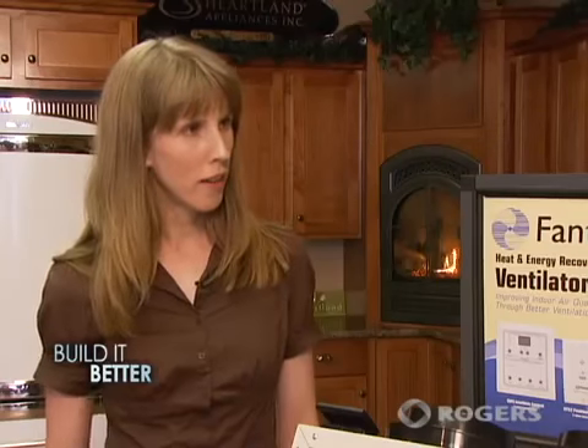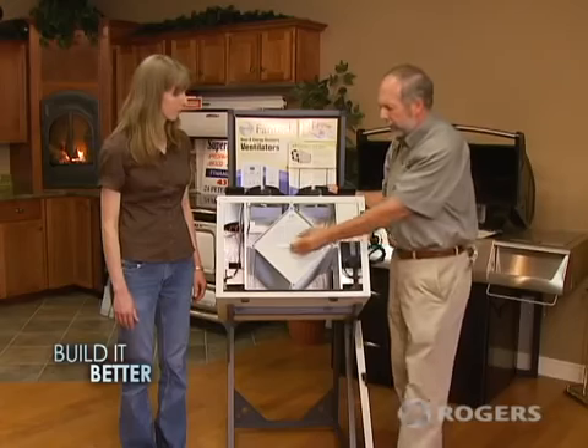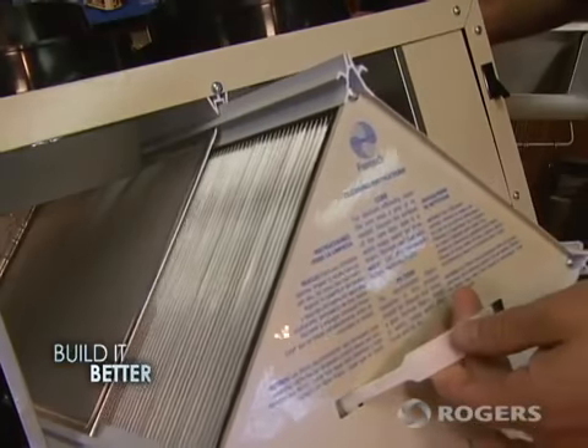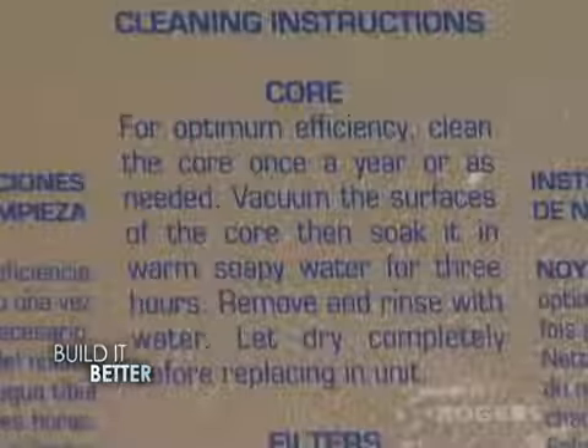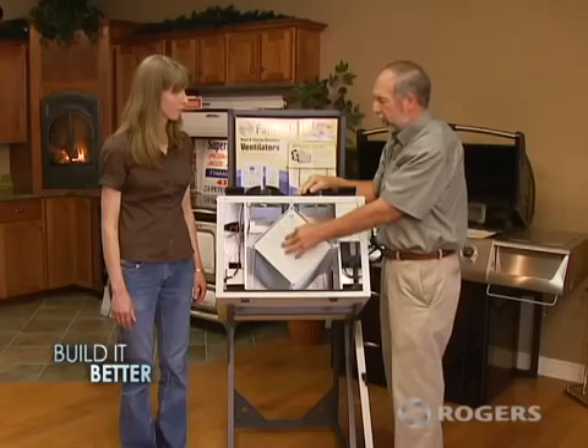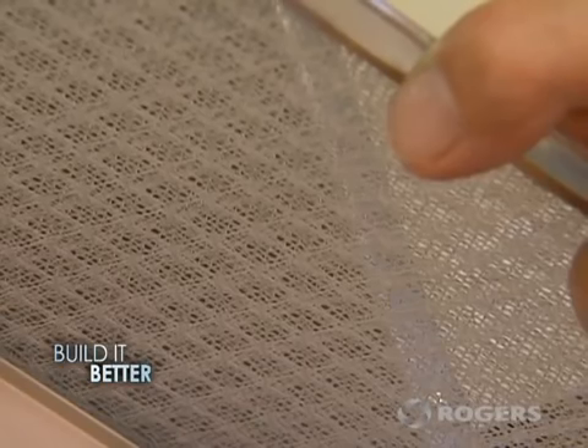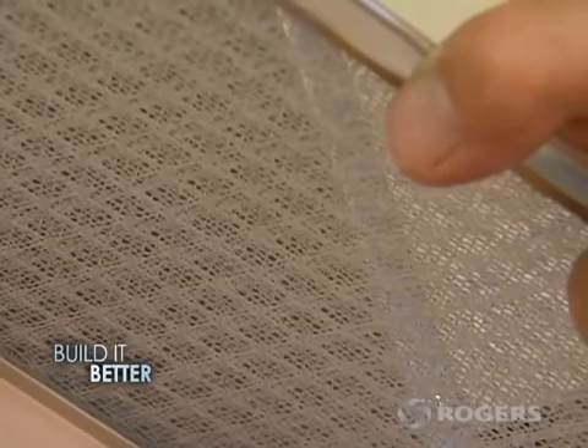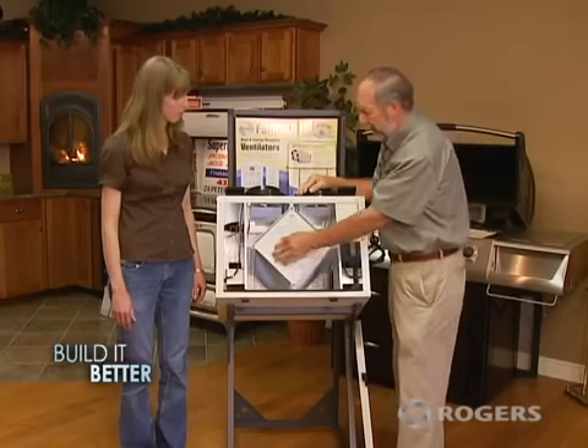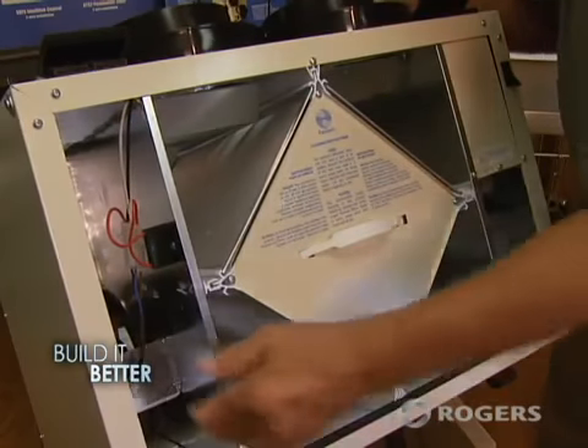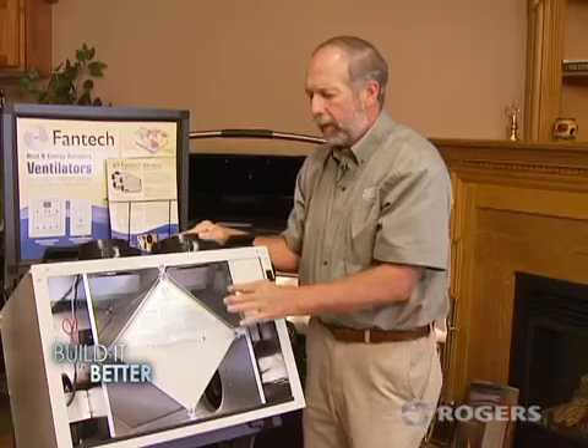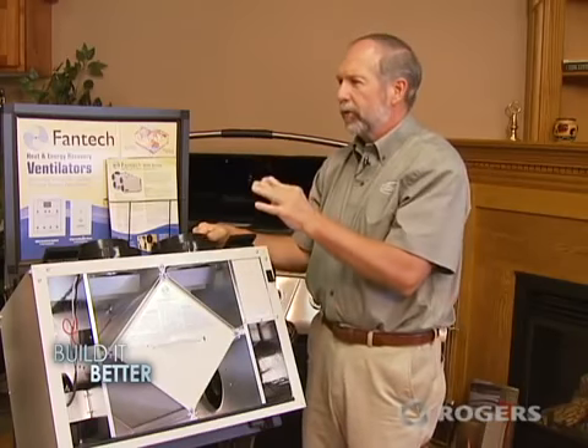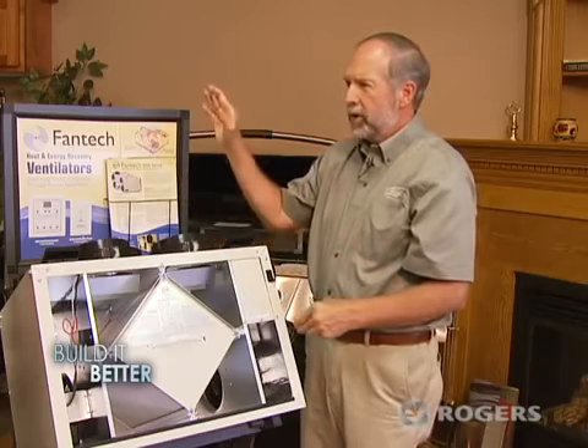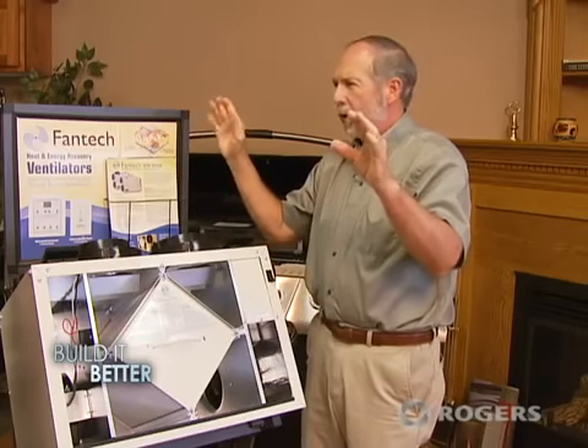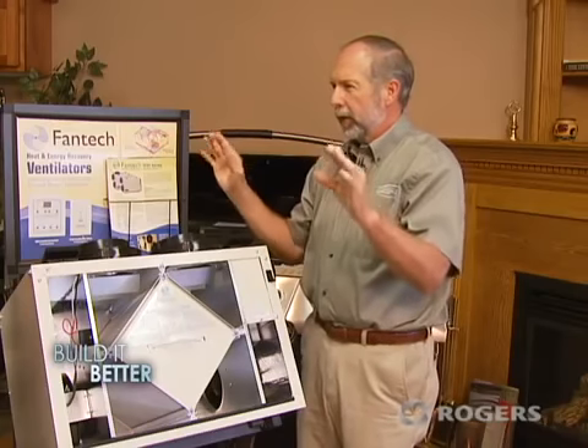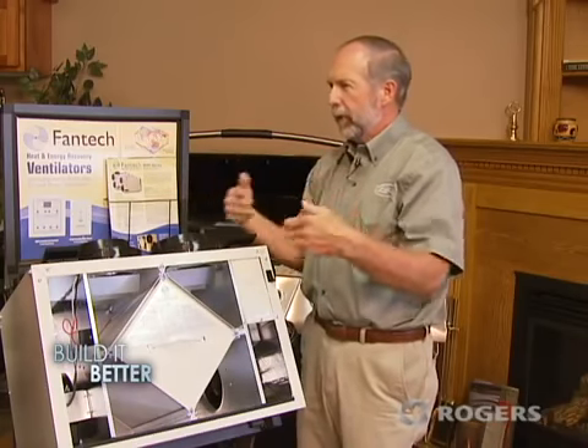Is there much involved with the maintenance? Maintenance is pretty simple. I pulled the core out here before. You can see in almost all models this is removable. The instructions are right here telling you to take that out once a year or so and clean it out. There's filters to pick up some of the dust and particles before they get into the core. Same thing, wash those, and you might do a little bit of cleanup inside the unit if there's any dust or particles in there. Other than that, the only thing you really need to look at is the outside hoods. On the outside of the building you'll have a fresh air and an exhaust air hood. Make sure at least once a year that they're not blocked by leaves or grass that could prevent free airflow.